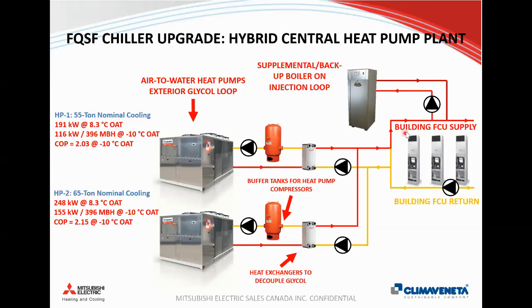This system's going to operate just on a simple changeover. So at first this was designed for 116 kilowatts and 155 kilowatts at -10, still with decent COPs. And if in the vertical stack fan coil system they get complaints from residents that there's not adequate heating, they're going to kind of dial back that cutout temperature to have a higher supply temperature to maintain indoor thermal comfort, which is the most important thing. And secondary to that, we want to fuel switch as much as possible.